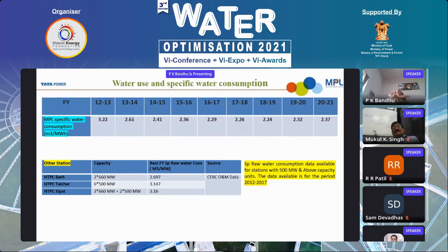So I wanted to show you the 3.5 liter per kilowatt hour, which is standard by the new water environment norms, and that is related to, I assume, 85% PLF. At 85% PLF, we have also achieved 2.1 liter per kilowatt hour.